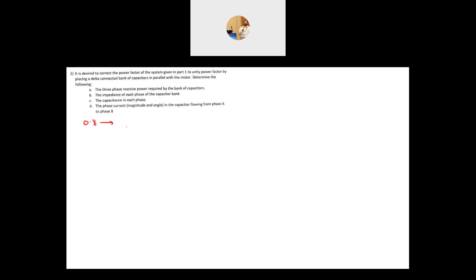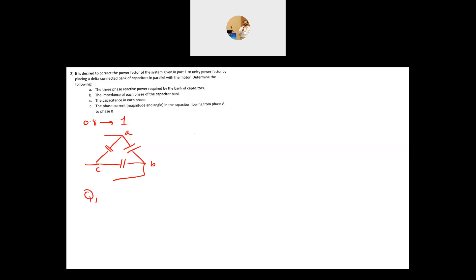To correct the power factor from 0.8 to unity, a delta-connected bank of capacitors is placed in parallel with the motor. For the power factor to equal 1, the total reactive power Q_total of the system must equal zero. Since Q_motor = 16,398 VAR, the capacitor bank must supply exactly Q_C = 16,398 VAR to cancel it.